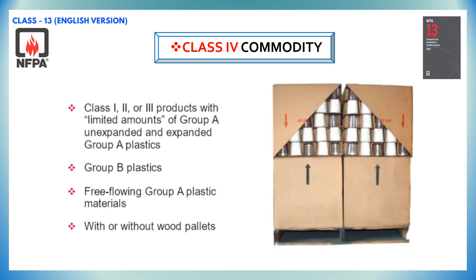Class 4 commodity classification is defined as a product that meets one of the following criteria: class 1, 2, or 3 products with limited amounts of group A unexpanded and expanded group A plastics. Also, if the products are constructed partially or totally of group B plastics, it will come under class 4 commodity. Apart from that, a product which consists of free-flowing group A plastic materials will also come under class 4 commodity classification.